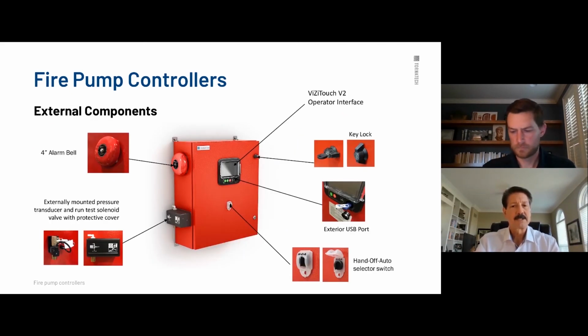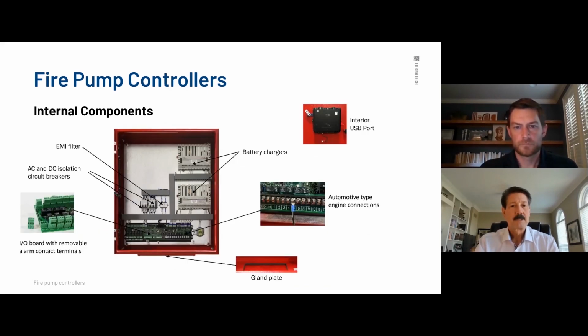Again, external, let's look at this. We're looking at typically, again, bell, externally mounted wetted parts, hand-off-auto selector switch, the operator, lockable door, externally accessible USB port that you can download all your data. Internal components, let's make it quick here, quite easy. We run our 120 or 240 into the terminal block, which runs into an EMI filter. We run it through an AC breaker, and then it feeds both of these chargers themselves.